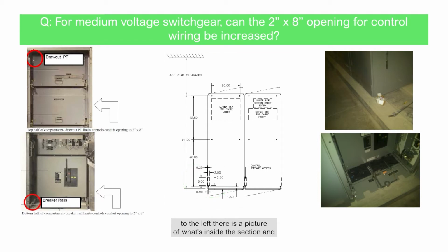If you look to the left, there is a picture of what's inside the section and what limits that from being expanded any larger. On the bottom of the section, you have your draw-out medium voltage breaker and the breaker rails. They extend from the front of the cabinet back to where the breaker locks into place. The 2 by 8 inches opening is on the left side of that breaker rail, which is circled in red, so you can't expand that any further. Otherwise, you wouldn't be able to draw out the breaker.